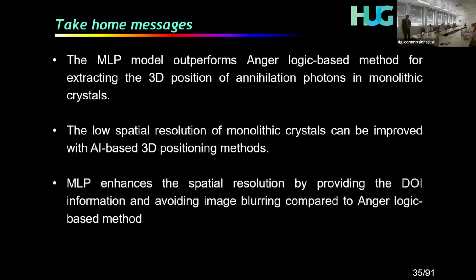So based on this study, we noticed the MLP model outperformed the Anger logic-based model for extracting the 3D position of annihilation photon and scintillation photon in monolithic crystals, and the low spatial resolution of monolithic crystal can be improved with AI-based 3D positioning method. And MLP enhanced the spatial resolution by providing the depth of interaction information and avoiding image blurring compared to Anger logic-based.